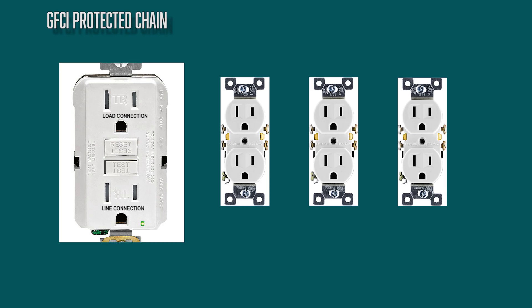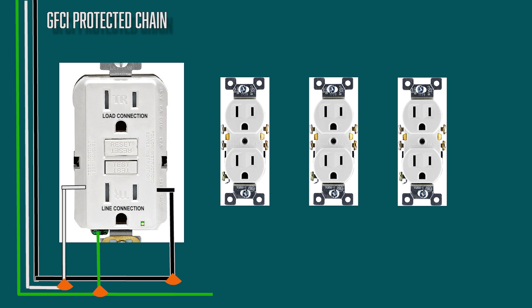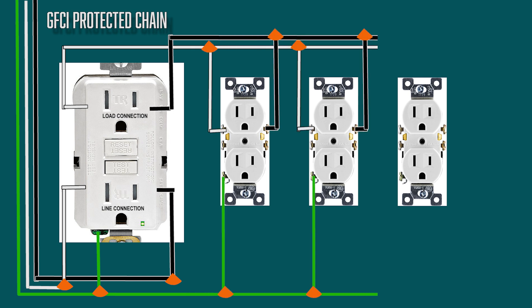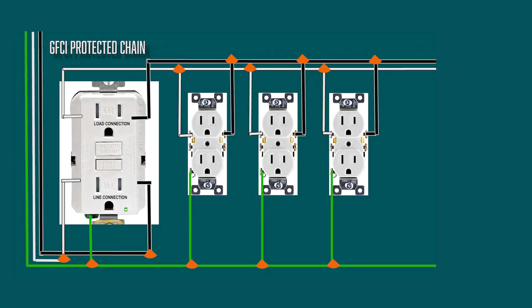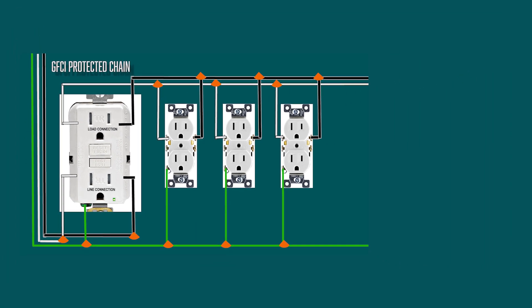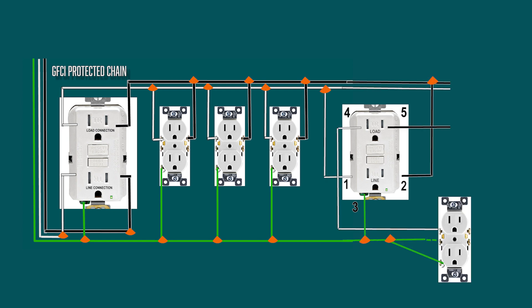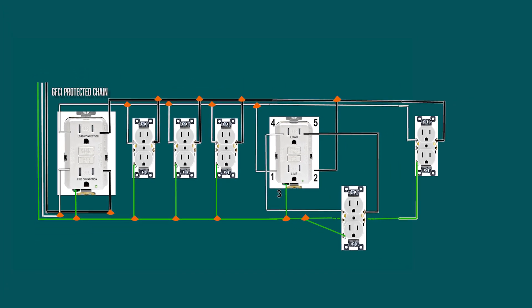One of the options allows the original GFCI to be connected with all of the wiring, and then it sends on just standard three wire line throughout. It will have three connections in each outlet throughout the whole chain. If you encounter another GFCI on the line that is forwarding the power, it will have five, and the last outlet in the line will always have just three connections. So by opening up the outlet, you can already tell what it is trying to do. Is it using power on its own, or is it feeding the power down the line?